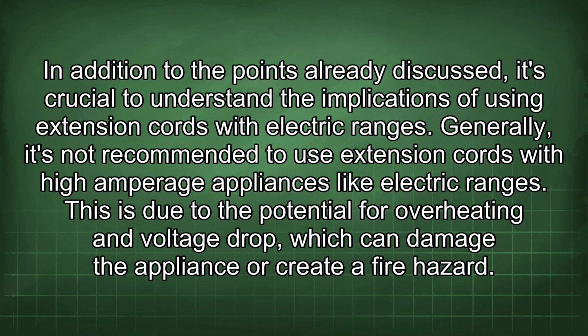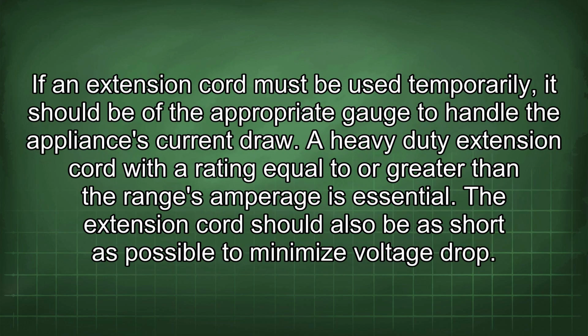In addition to the points already discussed, it's crucial to understand the implications of using extension cords with electric ranges. Generally, it's not recommended to use extension cords with high amperage appliances like electric ranges. This is due to the potential for overheating and voltage drop, which can damage the appliance or create a fire hazard. If an extension cord must be used temporarily, it should be of the appropriate gauge to handle the appliance's current draw. A heavy-duty extension cord with a rating equal to or greater than the range's amperage is essential.